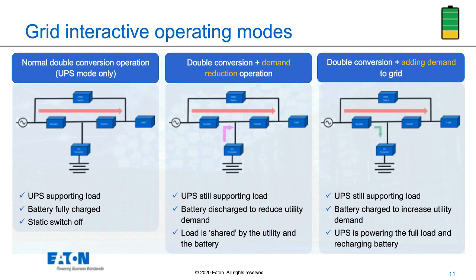When this is set up by the user or operator, a certain amount of battery time and capacity is held in reserve and never used by these programs. The client can always rest assured that I have, let's say, 10 minutes of battery backup time held in reserve for the critical load under any and all circumstances. If I use some of my extra battery capacity to support these programs, I do not touch that minimum level required for data center operation.